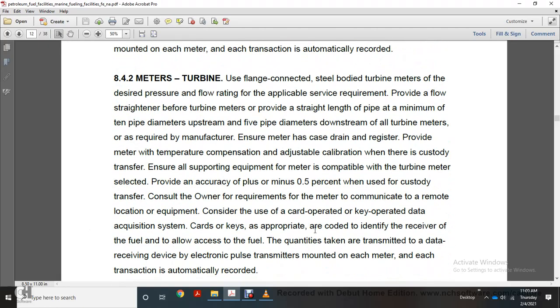Meters turbine. Using flange-connected, steel bodied turbines of the desired pressure flow rating applicable service requirement to provide a flow straightener before the turbine meter with the provided straight length of the pipe to minimum with a 10 pipe diameter upstream with the 5 pipe diameters downstream. All turbine meters are as required with the manufacturer. Ensure that the meter has the drain and register with the provide with the meter with the compensation adjustable calibration when there is custody transfer. Ensure all supporting equipment with the meter is capable of the turbine meter with the provide accuracy with a plus or minus 0.5% when used in custody transfer.